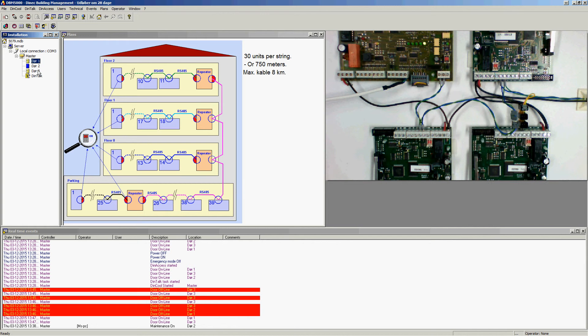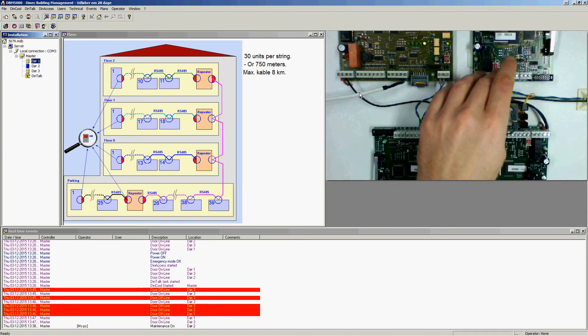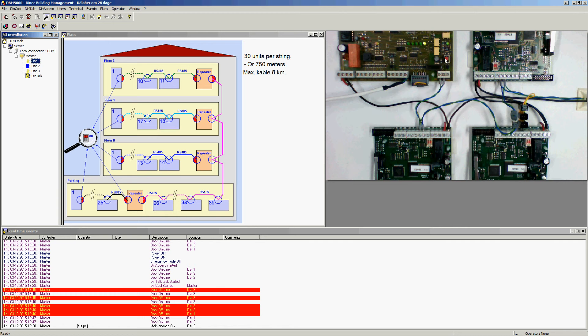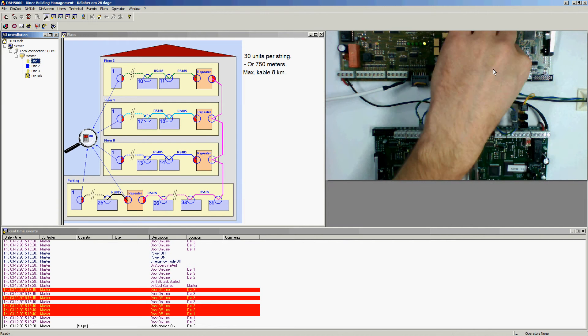Now, talking about how to terminate the bus — it is also indicated here in red which units are terminated. On my installation with a controller, followed by door, door, and the last door, I would terminate my controller and the last door, not the intermediate ones — that last door would be the end of the line, so its switches are up.